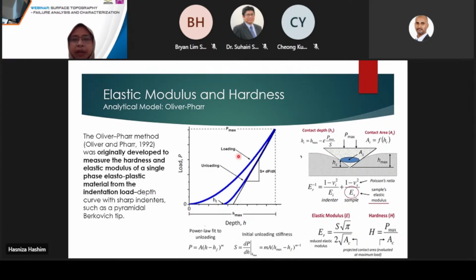So just now we have done the indentation. Now from the indentation testing, we have this force and displacement curve. This is the force and displacement curve from a single indent on fused quartz. As you can see here, the loading curve has a parabolic shape since the contact area between the probe and the sample increases as a square of displacement into the sample. Thus, more force is required to displace the probe into the sample.